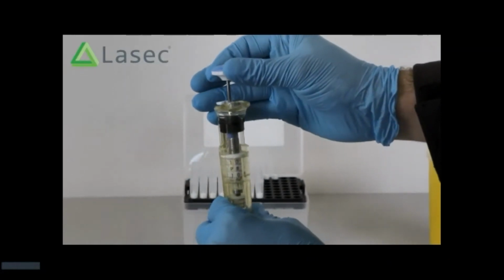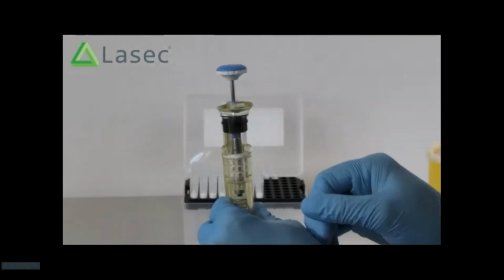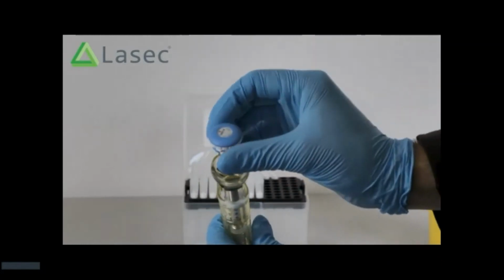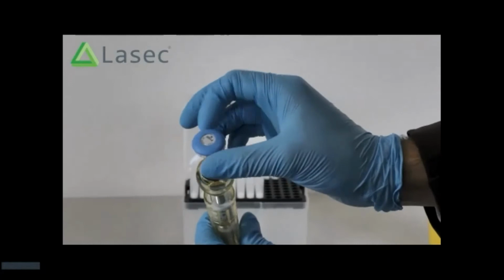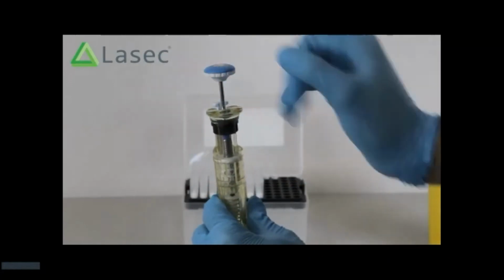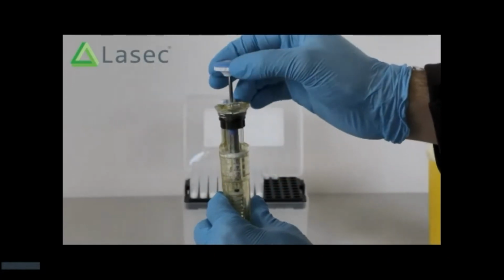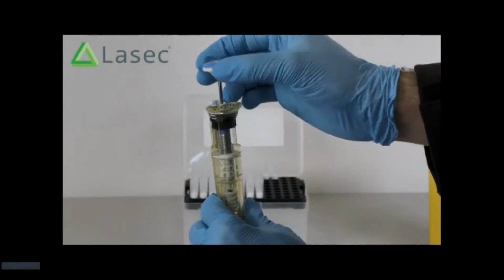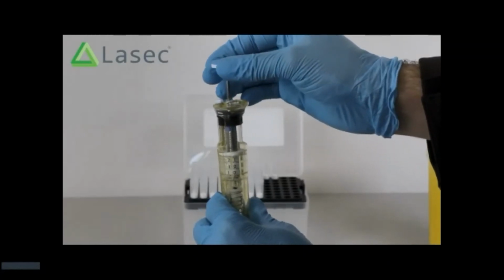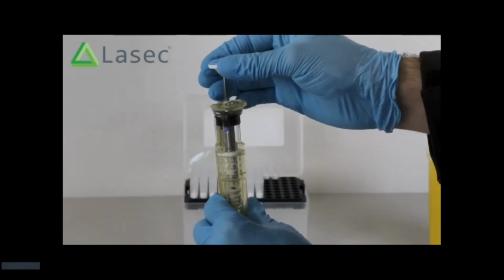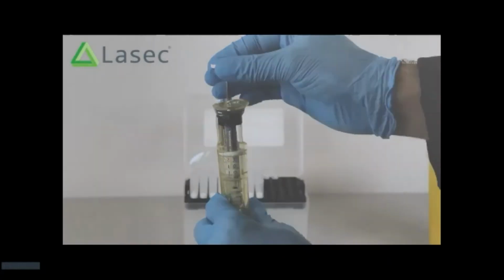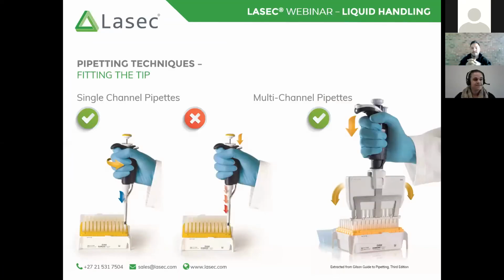Like I said right at the beginning, when explaining air displacement pipettes, the amount of air displaced by that piston is going to be equivalent to the amount of liquid aspirated. So you can assume that when you're decreasing that volume, the piston will be moving down. Conversely, if I was increasing that volume, I would need to increase the amount of air that's going to be displaced. So I would need to move that piston into its full position.